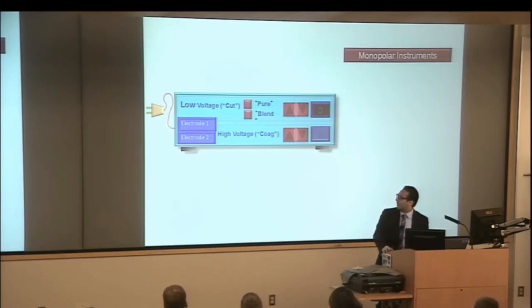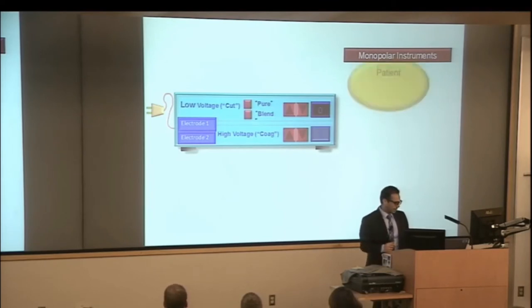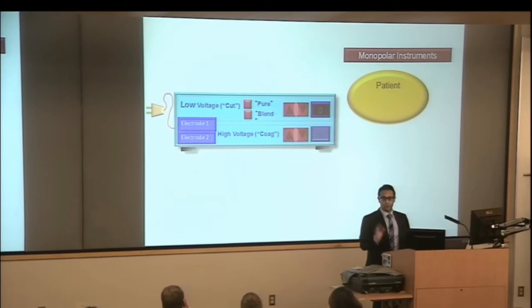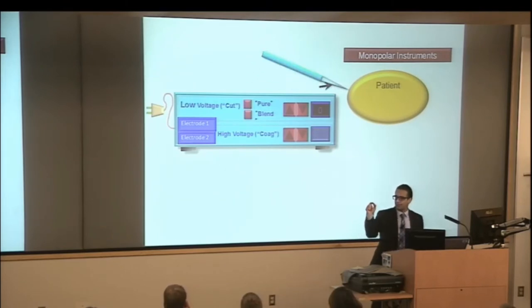Here we have an electrosurgical unit, a generator, and it's attached to the patient. We first demonstrate monopolar devices - this is the little tip, the active electrode, that's the term, and that's one electrode. The second electrode is this pad, and we always call it the grounding pad, but that's actually a misnomer.